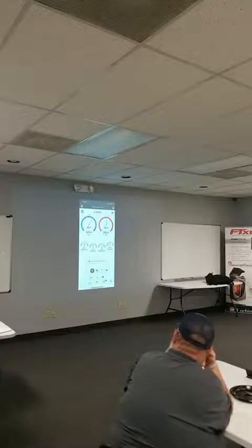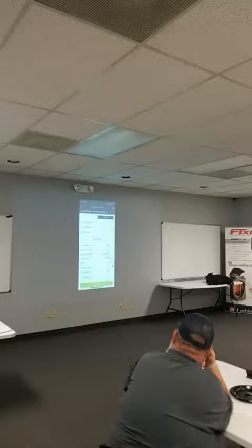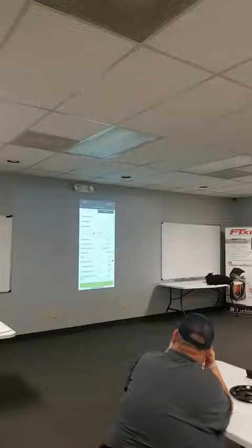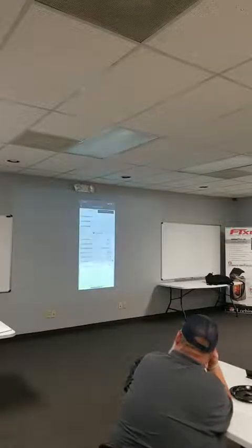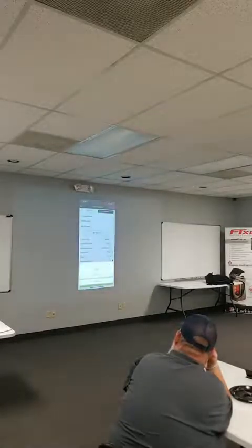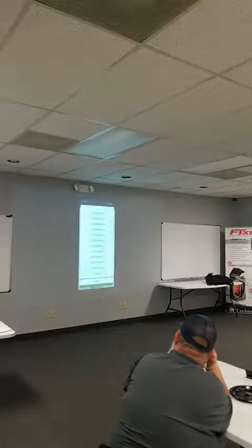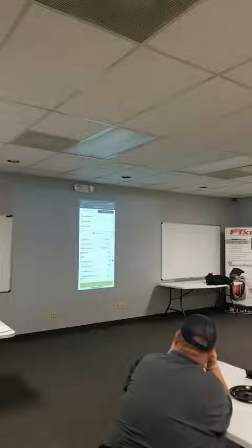That's a micro channel. So, by design, let's just start out with a profile here. Is that a TXV system? It is. All right, so it's looking for 3 tons. For the type of compressor, the first thing it's asking is a split system, yes or no. So this is actually a package system, it's got a scroll compressor, it's 3 tons of cooling, it's 410A, it's 13 to 16 SEER with a TXV, and we use the default superheat and subcooling target of 10, okay?